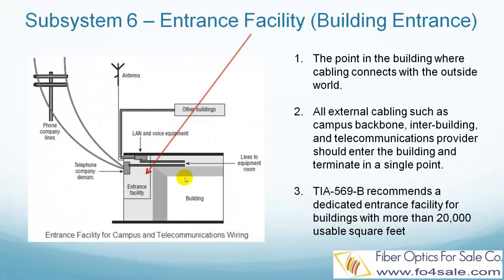The entrance facility specifies the point in the building where cabling connects with the outside world. All external cabling such as campus backbone, inter-building, and telecommunications provider connections should enter the building and terminate in a single point. TIA 569B recommends a dedicated entrance facility for buildings with more than 20,000 usable square feet.